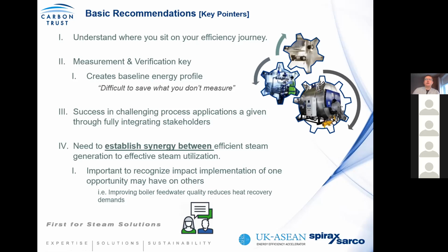It's also important to understand the synergy between steam generation and utilization, because the ability of a boiler to generate steam determines how you consume steam. And it's also important to recognize, I've seen from one of the polls, there's a high interest in projects and energy opportunities. But what you'll find sometimes is the impact of one project may influence another. So for example, if you improve your feed water quality, you're going to reduce your blowdown demands and the ability to recover energy from blowdown, boiler TDS blowdown, sorry. However, what is also worth noting is that you can learn from each other.